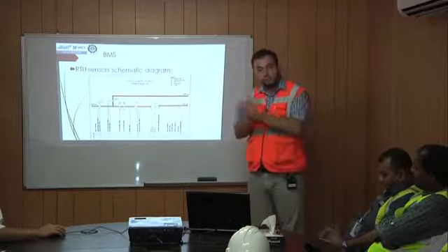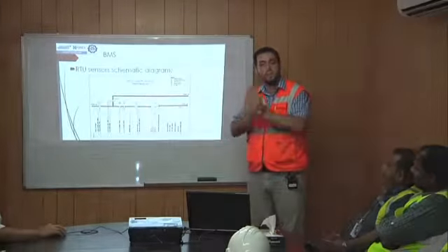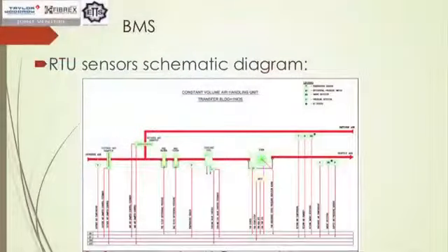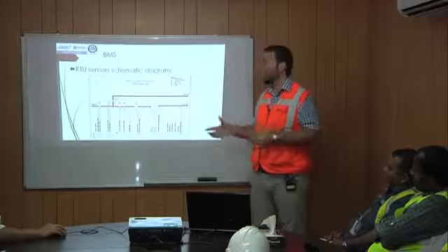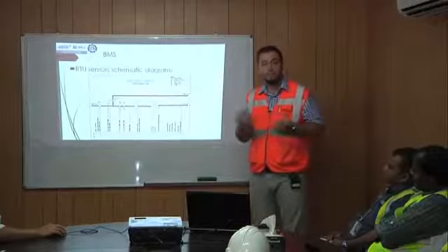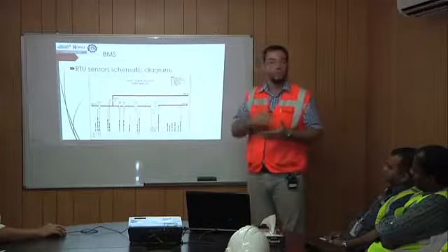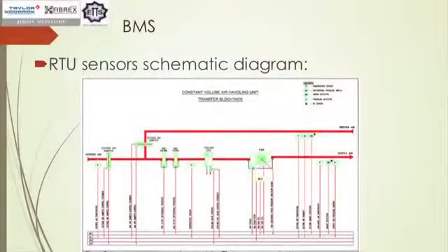So across your 2-inch filter, which is washable, which you can remove and you can change it, you've got a pressure sensor which shows on the BMS whether it needs cleaning, whether it needs removal. And we've got one across the bag filter, which is the major one. It will show the pressure difference, and accordingly you will know whether you need to replace it, whether you need to take it out, or whether it is still very suitable for operation.